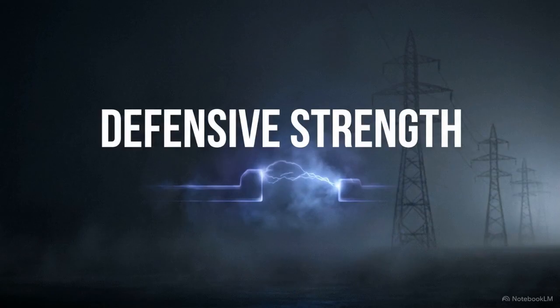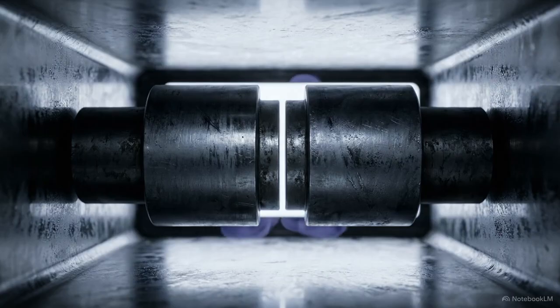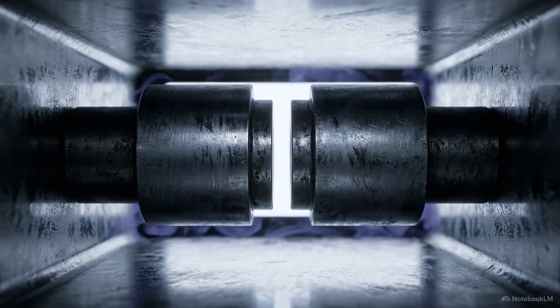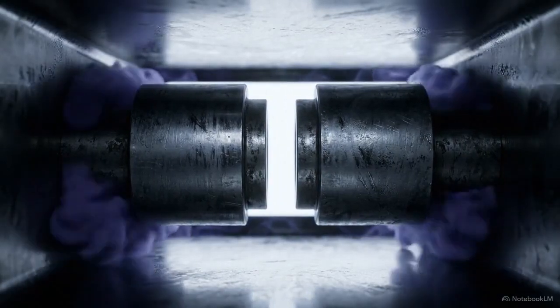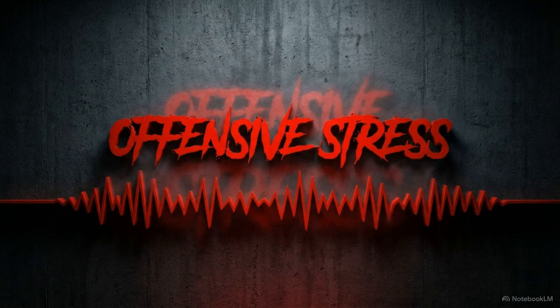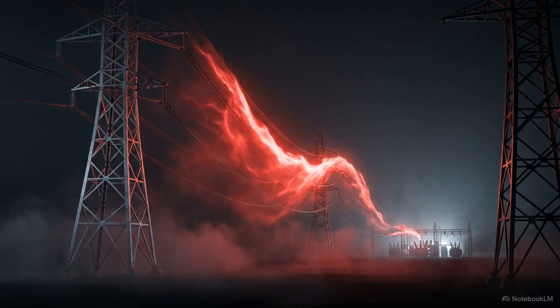The breaker's defense is the rate of recovery of dielectric strength. This is the speed at which the insulating medium, whether it's sulfur hexafluoride, air, or a vacuum, can reclaim the space between the contacts. Pushing against that is the grid's offensive line, the rate of rise of recovery voltage. This dictates both the speed and the peak amplitude of the voltage slamming back into those contacts.